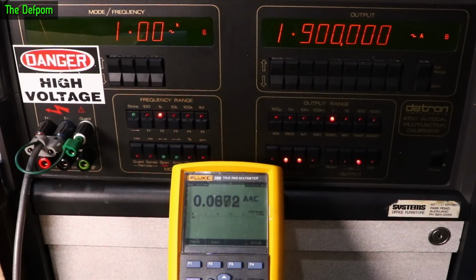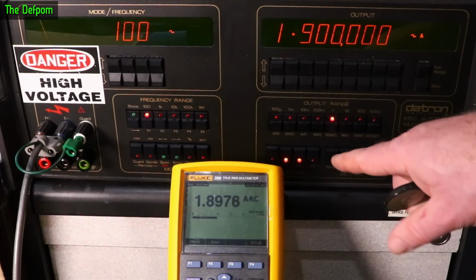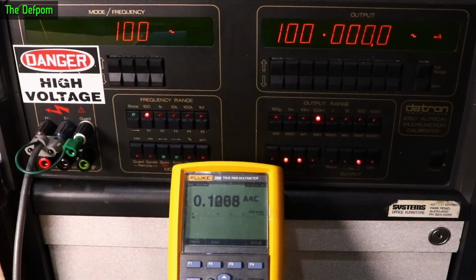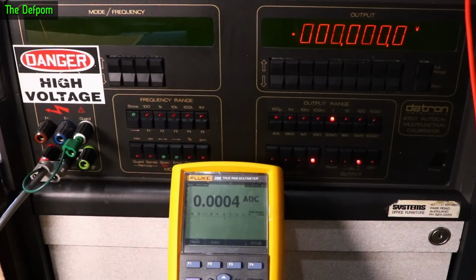Let's do 100 hertz and we'll go back down again. Looks about the same, slightly better. Let's do 100 milliamps. Yeah, it's basically the same as it was before the other frequency. Now I do actually have a high current calibrator up here. It's a transconductance amplifier. So I need to hook up to that and we'll do something a bit more than 1.9 amps.